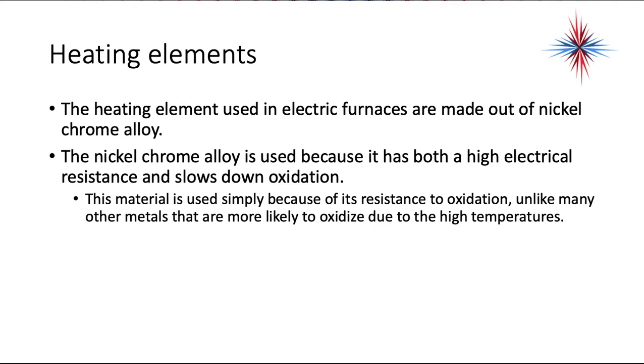The heating elements used in electric furnaces are made out of nickel chrome alloy. The nickel chrome alloy is used because it has both high electrical resistance and slows down oxidation. The material is used simply because of its resistance to oxidation, unlike many other metals that are more likely to oxidize due to high temperatures.